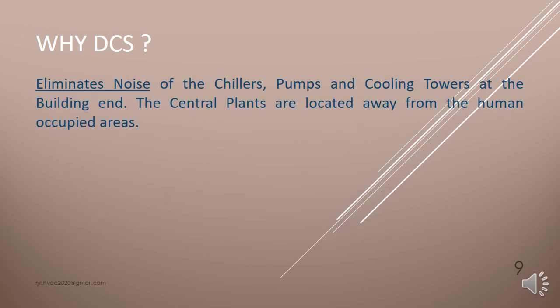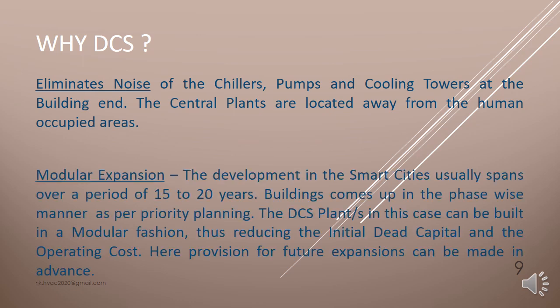Why DCS? Eliminates noise of the chillers, pumps, and cooling towers at the building end. The central plants are located away from the human occupied areas. Modular expansion. The development in the smart cities usually spans over a period of 15 to 20 years. Buildings come up in a phase-wise manner as per priority planning. The DCS plants in this case can be built in a modular fashion, thus reducing the initial dead capital and the operating cost. Here provision for future expansions can be made in advance.